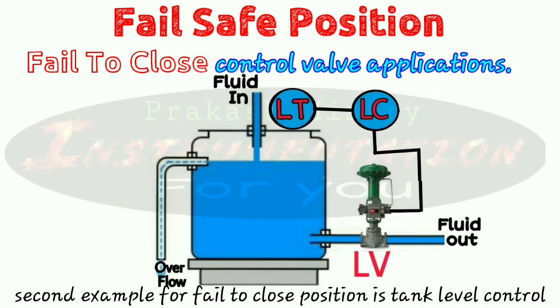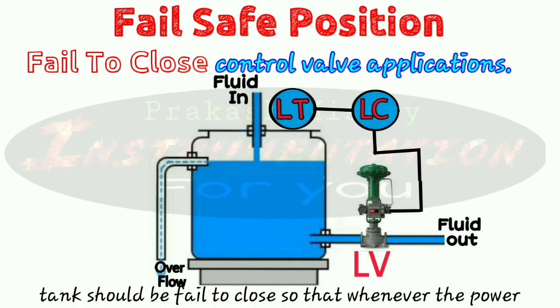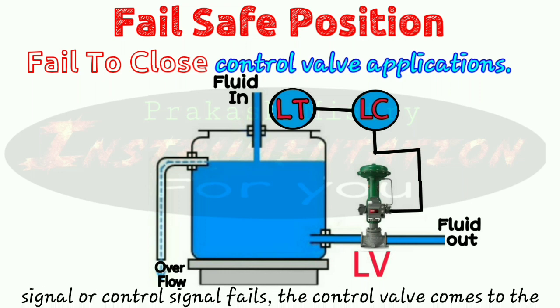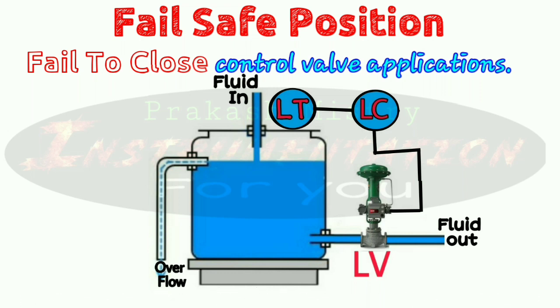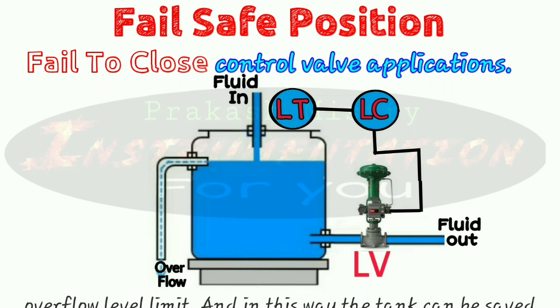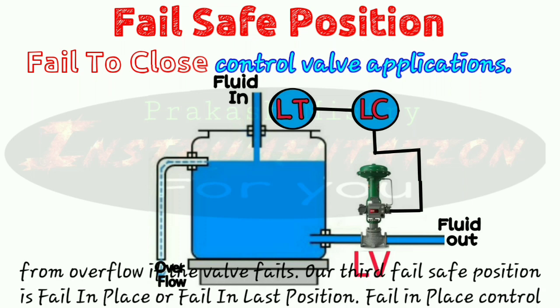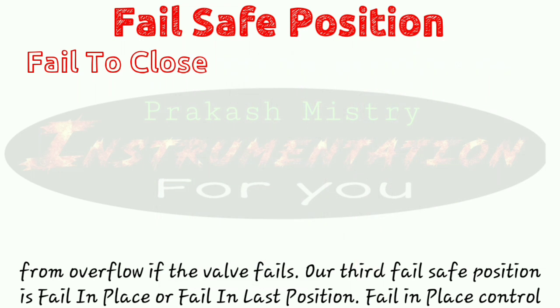Our second example for fail to close position is a tank level control valve. The control valve that controls the level of the tank should be fail to close, so that whenever the power signal or control signal fails, the control valve comes to the fully closed position. Then the tank level remains below the overflow limit, and in this way the tank can be saved from overflow if the valve fails.